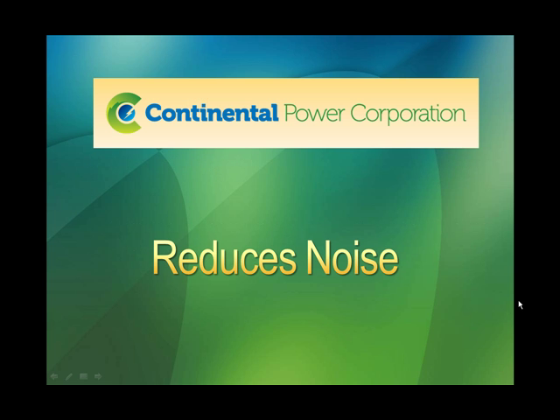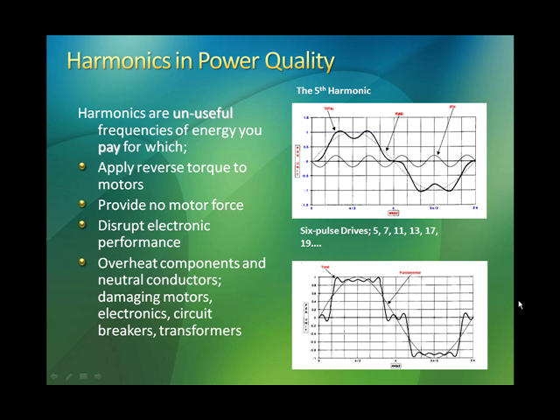Now let's take a look at the second feature that the PowerWorx has within it. We reduce surges and spikes. We secondarily reduce noise. A very common form of noise in electrical distribution systems is called harmonics. These are unuseful frequencies of energy you pay for, which apply reverse torque to motors. They provide no motor force. They disrupt electronic performance. They overheat components and neutral conductors. Typically, when you have noise and harmonics in the system, you will see the current in the neutral conductor go up significantly.